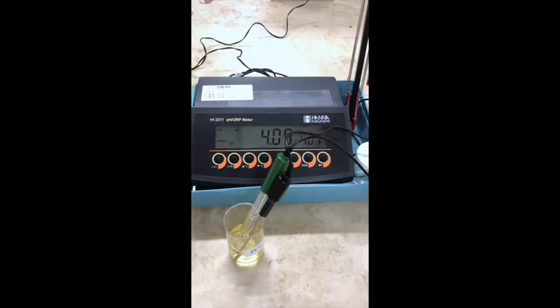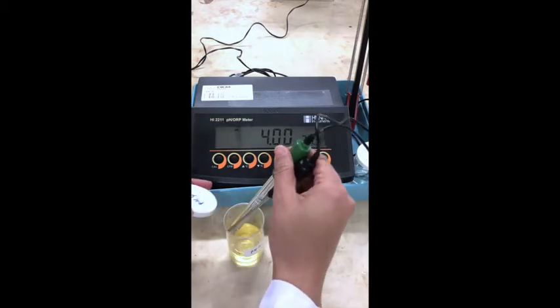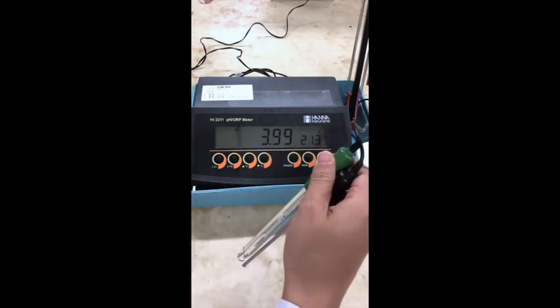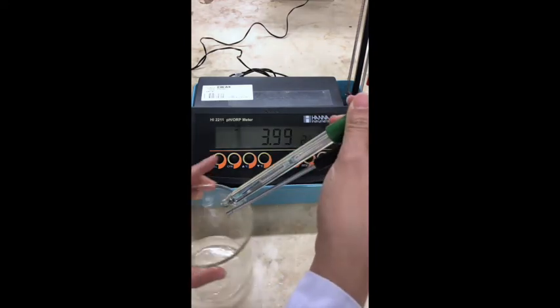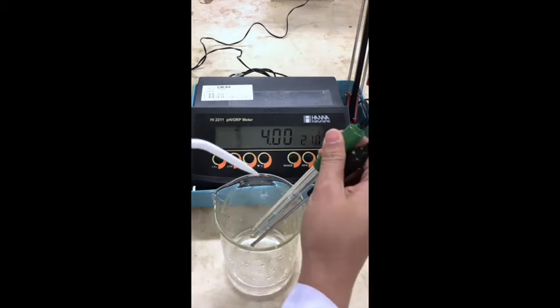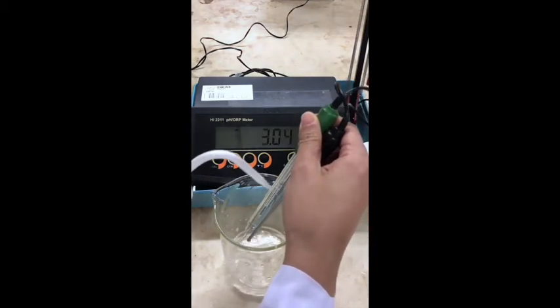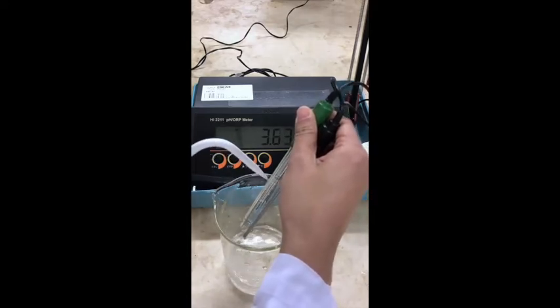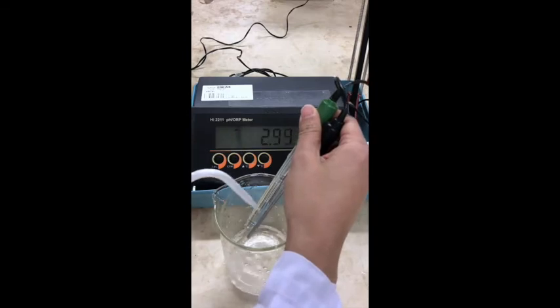Once the ready icon is indicated, press the CFM button again, and the display is changed. There's no CAL icon, which means the calibration process is finished, and this is the measurement mode. And now the calibration process is complete. Let's move the electrode and thermocouple into the sample solution. Before that, remember to rinse the electrode and thermocouple again and remove the surface water to prevent the dilution of the sample.